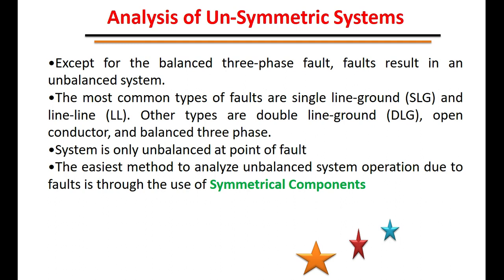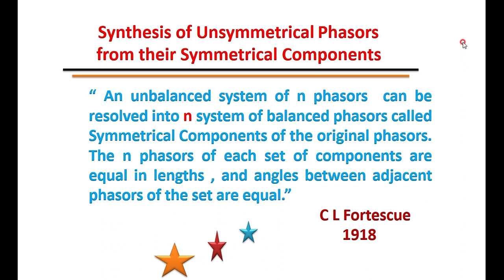Because of the single line-to-ground fault, unbalance occurs. The system is only unbalanced at the point of the fault. Because of this unbalanced fault, the currents are different and phase angles are not equal. The easiest method to analyze this type of unbalanced system operation due to fault is through the use of symmetrical components. This is what C.L. Fortescue stated regarding the symmetrical component method — the synthesis of unsymmetrical phasors from their symmetrical components.